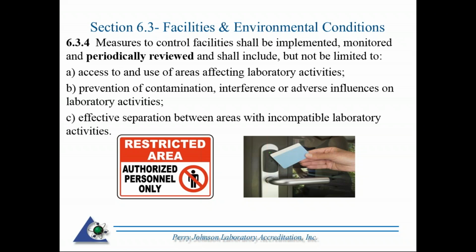An example I've tried to depict down there: perhaps in order to comply with this, a sign was posted outside the door. Periodically going back, looking at what was in place to comply with this standard, there may be additional personnel who have been observed going into the area that perhaps disturbed the testing. Hence, this perhaps would warrant a card reader, to depict a change that needs to be made based on periodic review of this particular requirement.